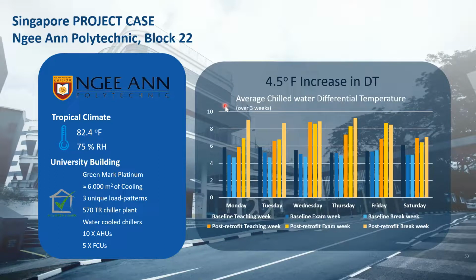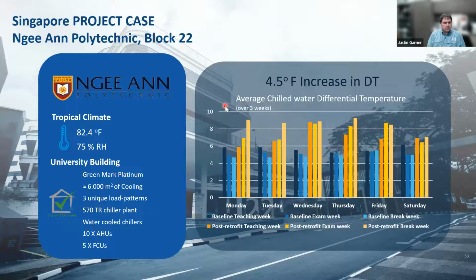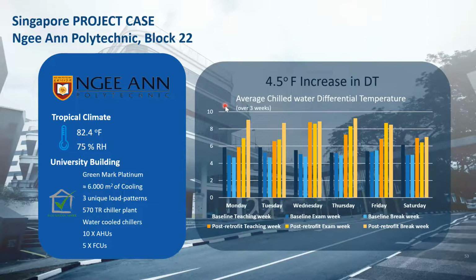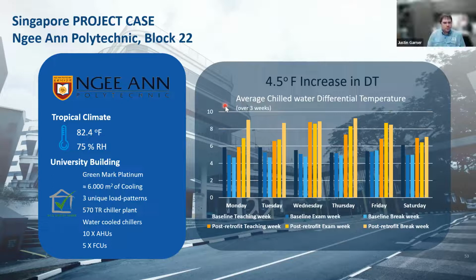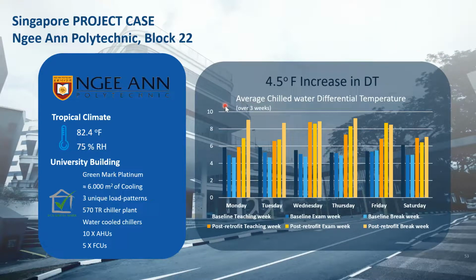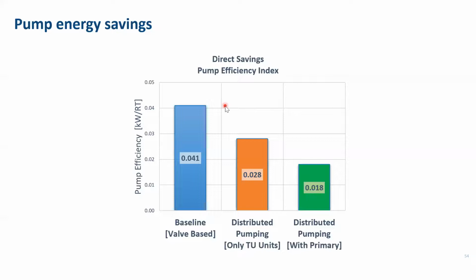We saw an average of 4.5 degree increase in delta T. So we, as a pump manufacturer, talk about the energy savings associated with the distributed pumps and what it takes to move that hydronic energy around the building. But in this case, we were able to improve the overall chiller efficiency by almost 3%, which is, dollars and cents wise, a much bigger number, even though it's a smaller percentage.